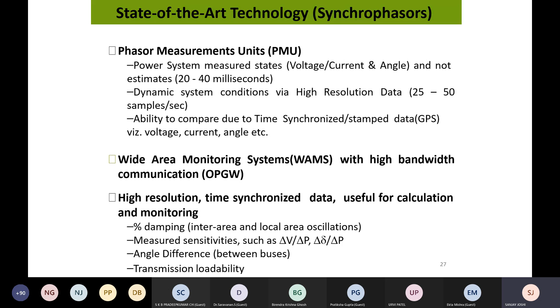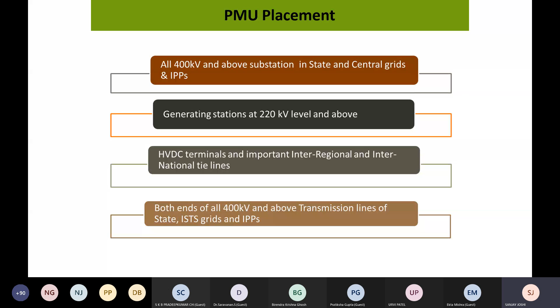Let's talk about PMU placements. All 400 kV and above in state and central grids and IPPs, independent power producers. Generating stations at 220 kV and above, HVDC terminals and important inter-regional and international tie lines. Both ends of 400 kV and above terminal lines of state, ISTS, interstate lines, grids and IPPs. So these are the locations, nodes where PMU placement is supposed to be there, and in India now it is a good state that the deployment of PMU is done at many buses. Almost the ones mentioned in these 4 points are covered now.